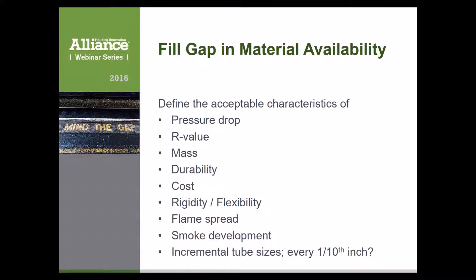There's an optimum condition we've already seen in our work, and we expect feedback on that from time-and-motion studies. We also need to address flame spread and smoke development. We're using PVC as a surrogate in testing, and while we'll push to see how far PVC can go, we recognize that current industry standards have flame spread and smoke development limitations that will need to be incorporated into the material spec. We may also look at incremental tube sizes beyond just two, two-and-a-half, and three-inch round duct.